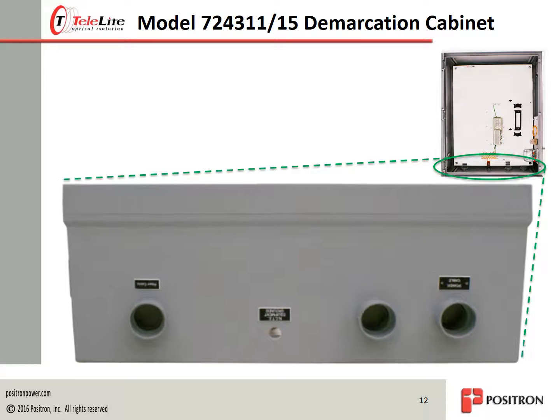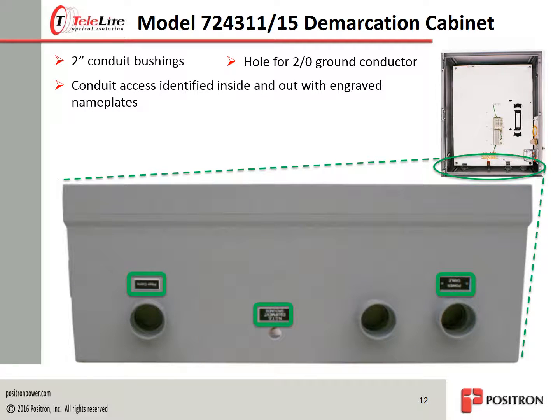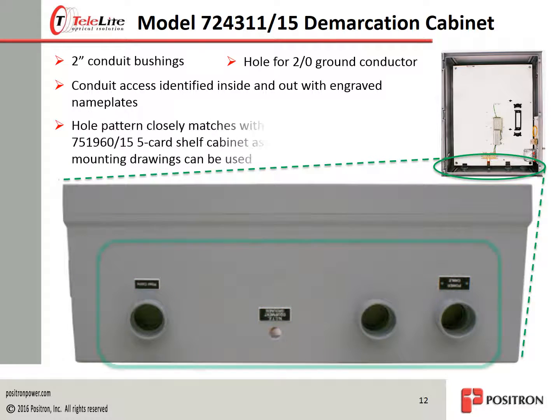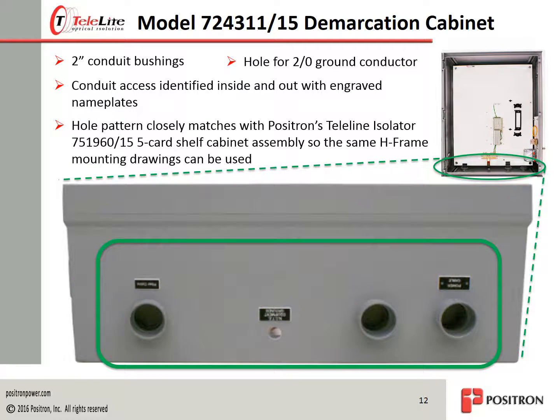Positron's demarcation cabinets feature pre-installed bushings to accommodate 2-inch conduits. The hole for the ground conductor is sized for a maximum 2-aught ground conductor. Conduit designation is indicated with engraved adhesive nameplates inside and out. The hole pattern closely matches the conduit hole pattern of the Teleline Isolator 5-card shelf cabinet assembly 751960/15. This enables the power company to use the same H-frame mounting and conduit entry designs created for mounting a Teleline Isolator cabinet assembly.